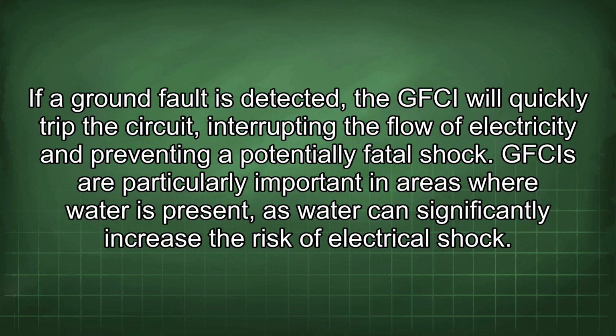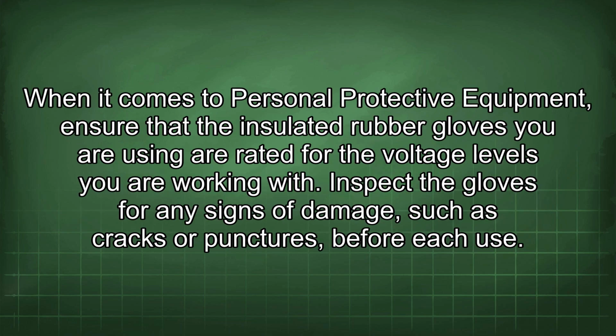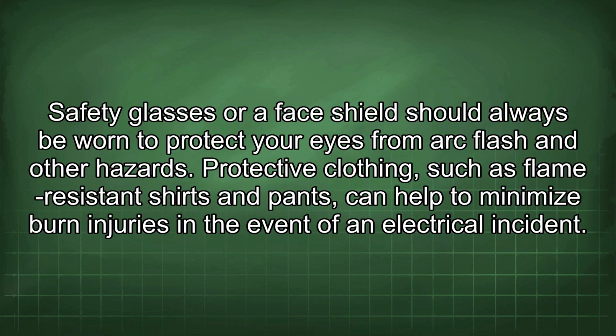When it comes to personal protective equipment, ensure that the insulated rubber gloves you are using are rated for the voltage levels you are working with. Inspect the gloves for any signs of damage, such as cracks or punctures, before each use. Safety glasses or a face shield should always be worn to protect your eyes from arc flash and other hazards. Protective clothing, such as flame-resistant shirts and pants, can help to minimize burn injuries in the event of an electrical incident.